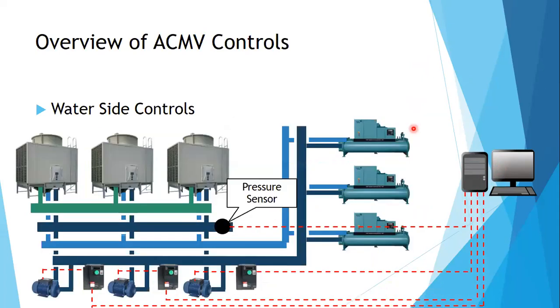Next, same scenario with your cooling tower side. Your cooling tower side also has pressure sensors. Same scenario again. When one of the chillers is turned off, the pumps will receive a signal from your BMS or from your PLC saying that the pressure is too high, the pumps need to lower down, need to slow down through the VSD.